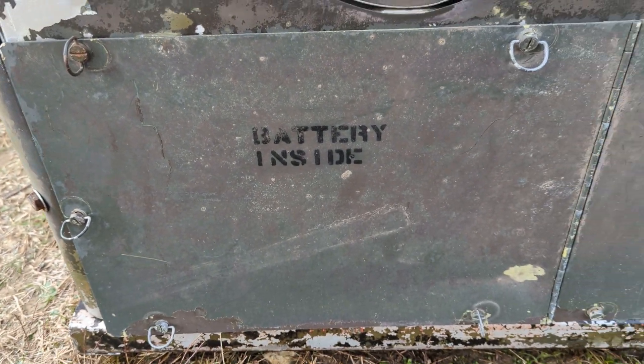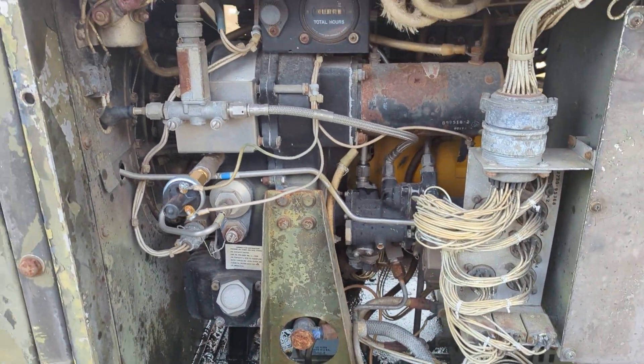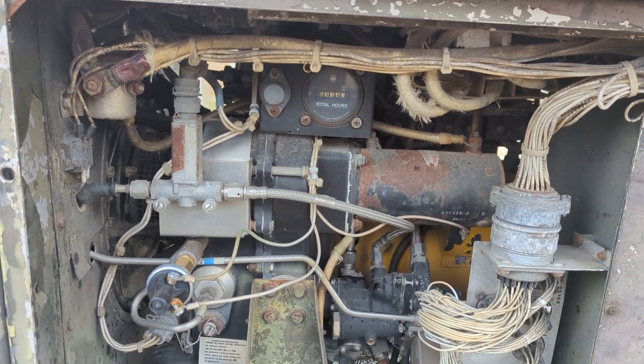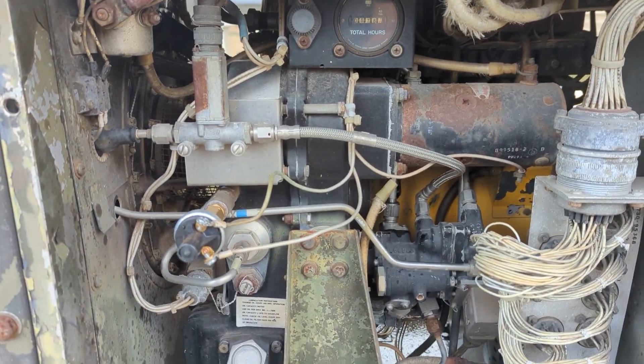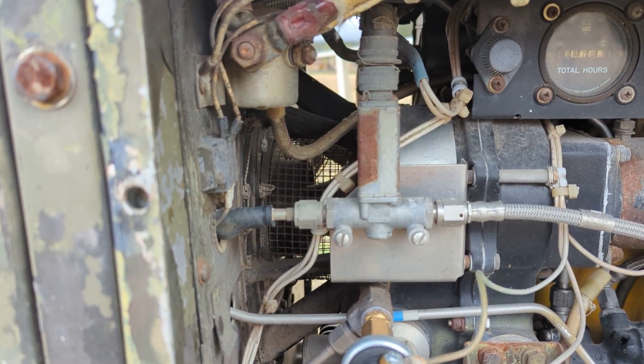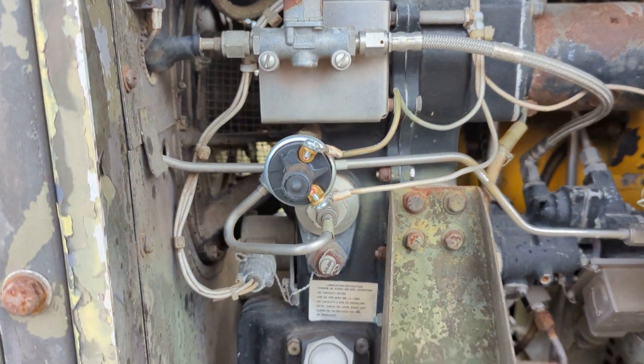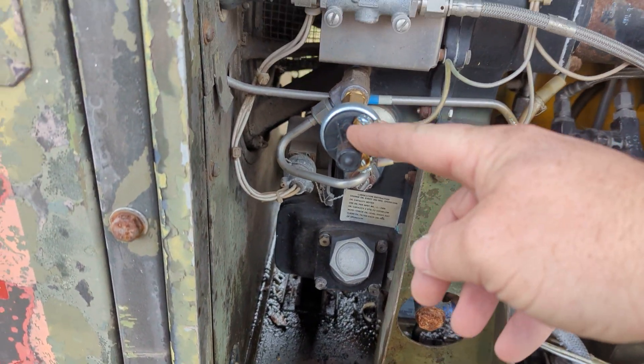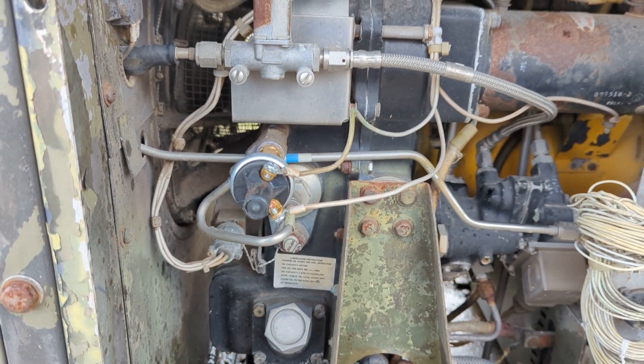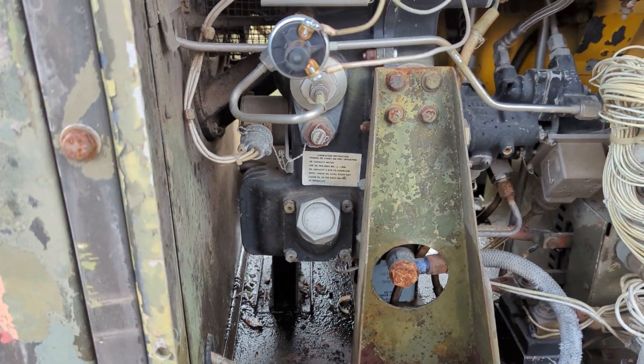Inside there is the battery compartment. Moving around — this side is the starter right there. On the right, an hour meter. This is the fuel shutoff. Right there with that screen is the intake for the engine. This is the oil pressure switch that drives the fuel solenoid to allow fuel to flow in. And here is the tach gen for running the percent RPM indicator.